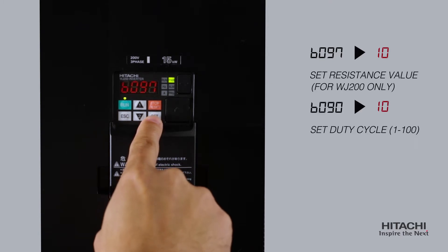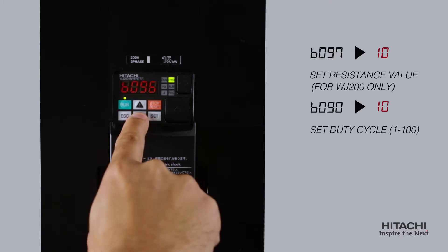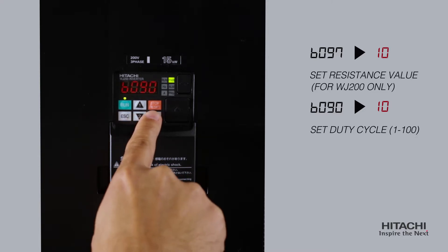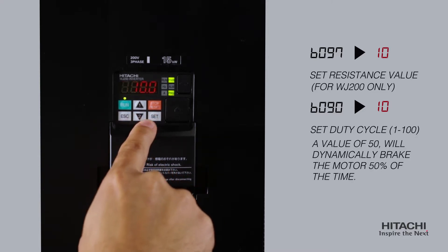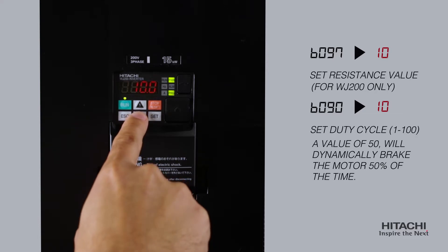Set B90 to a duty cycle from 1 to 100. A value of 50, for example, will dynamically brake the motor 50% of the time. This value will be limited by the selection of B97.